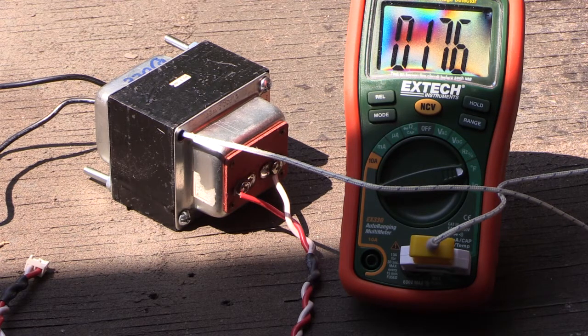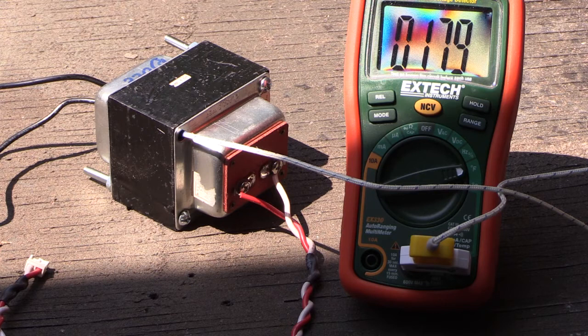And at some point, I think, if we left it long enough and created a more realistic installation as it would be in your wall, I think it's going to go up and up and up, and eventually I'm pretty sure the insulation on the magnet wire is going to fail, it's going to short out, and I think that's when you get the smoke and the sparks and the flames and the running and screaming. So is it really worth it? Is it really worth taking a chance to burn your house down because you didn't want to pay a few dollars to get your transformer fixed?